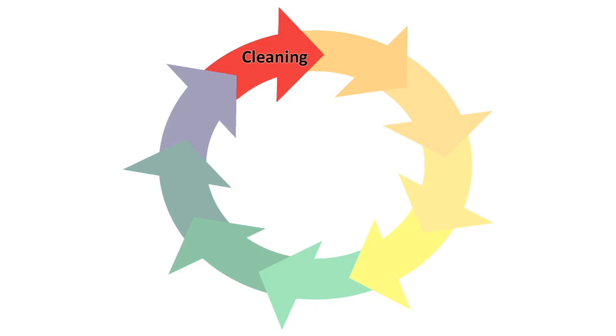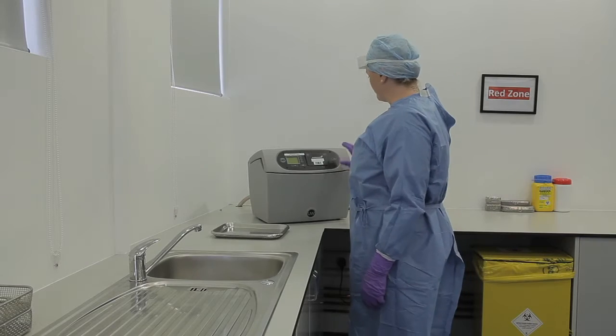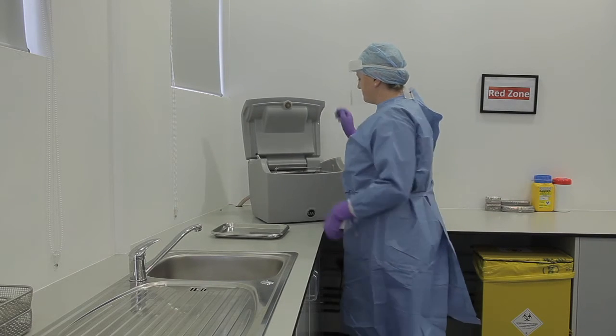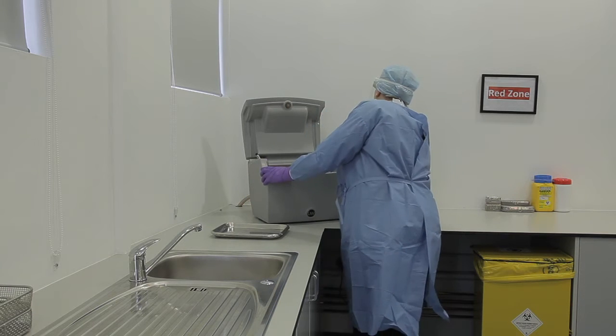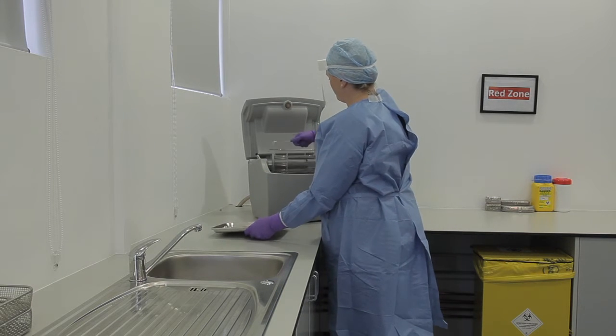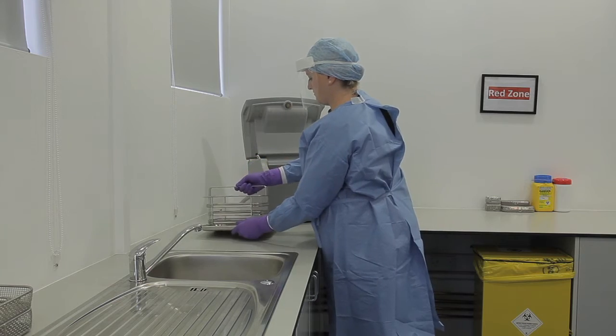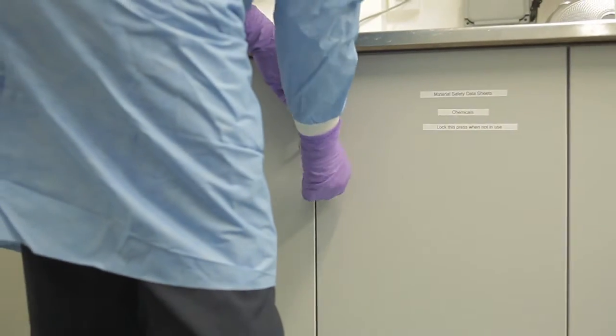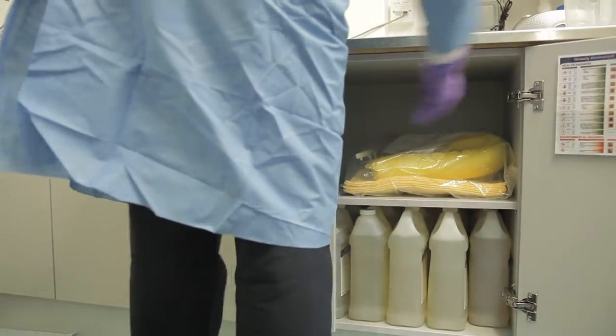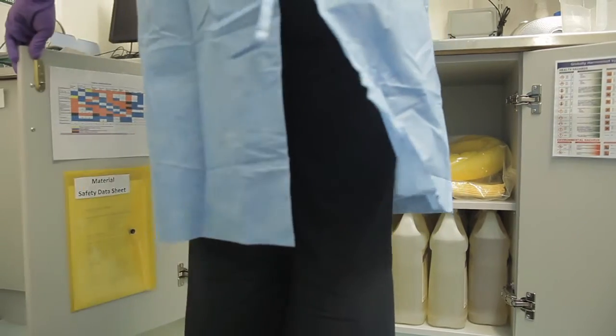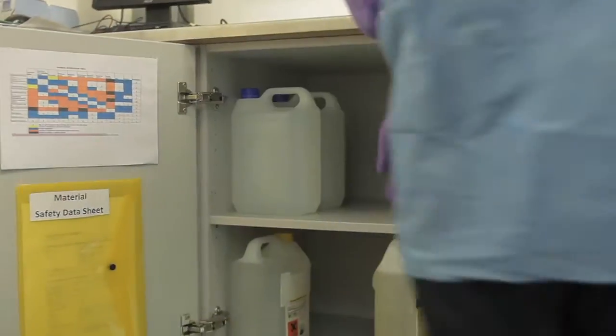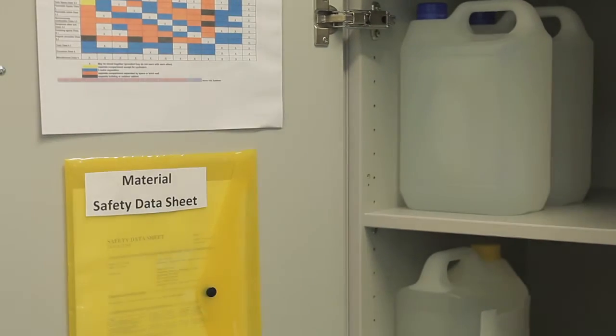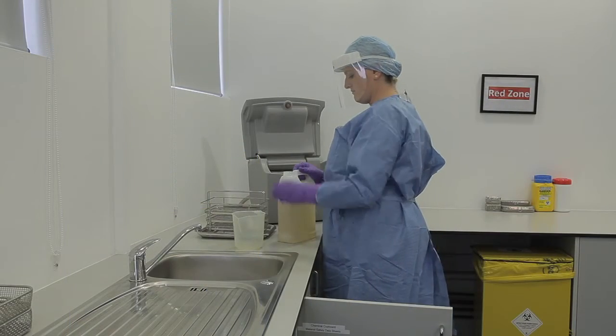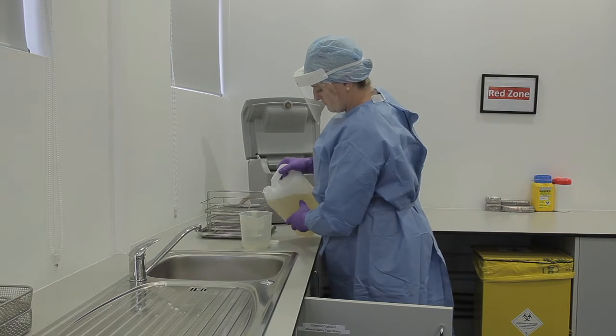The dental healthcare worker turns on the ultrasonic bath, closes the drainage valve, adds the appropriate measure of cleaning agent, for example detergent or enzymatic cleaner, for the machine and fills the ultrasonic bath with water. Follow manufacturer's instructions regarding the type of water and cleaning agents to be used in the ultrasonic bath. This may be tap water or water produced by a reverse osmosis unit. In the LDU, chemicals should be stored in a designated lockable cupboard, which should be clearly labelled. Copies of safety data sheets for all chemical agents used in this area should be readily available.